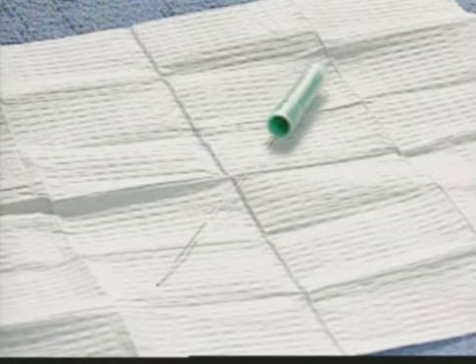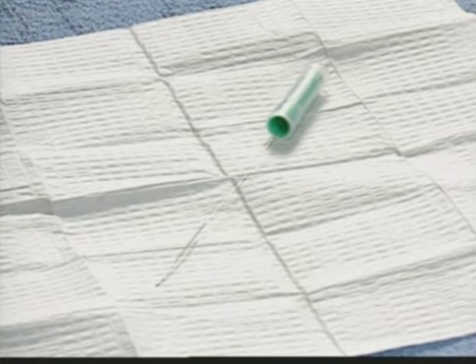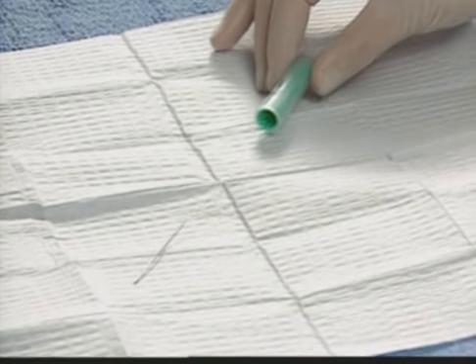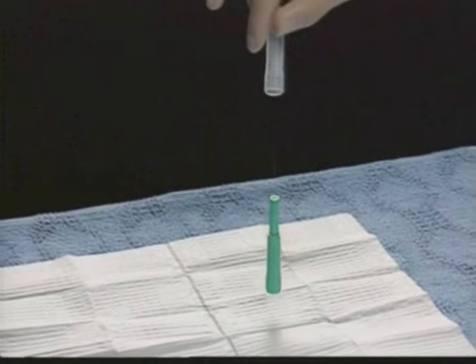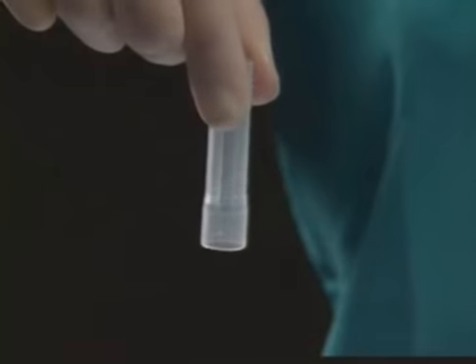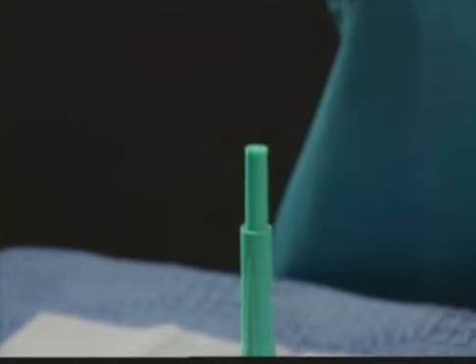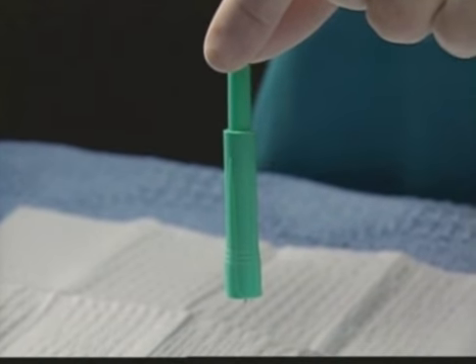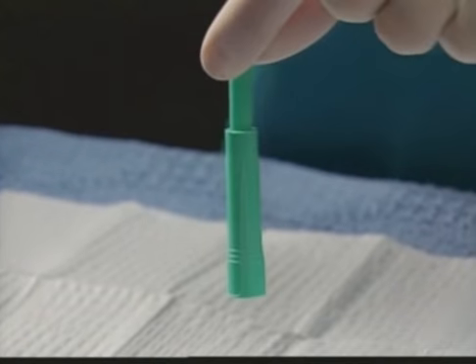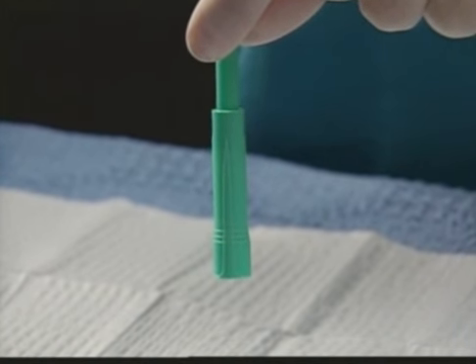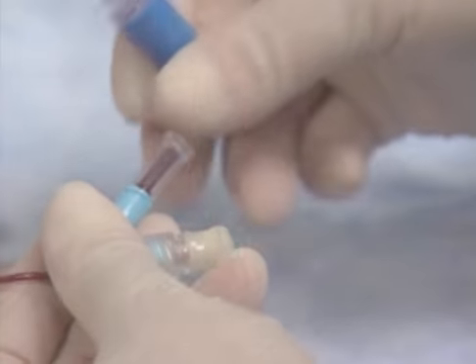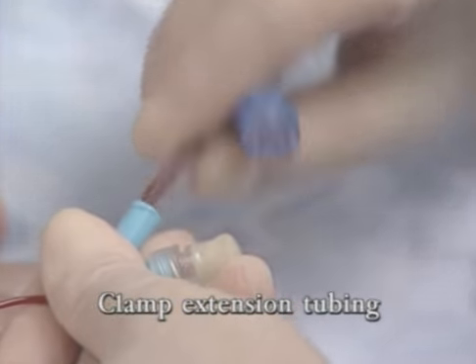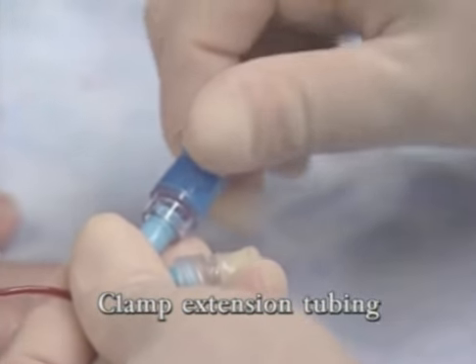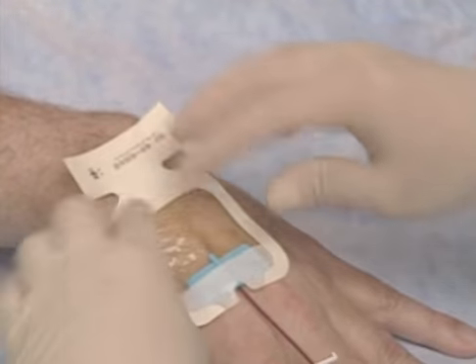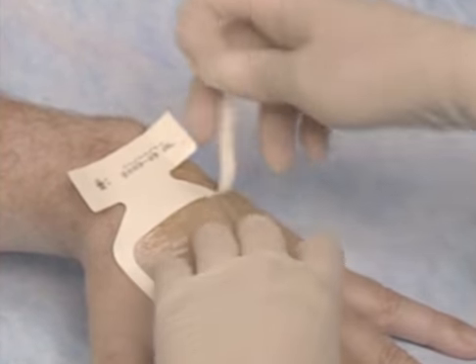If for some reason the needle is not shielded after removal, grasp the pebbled end of the white safety shield, allowing the needle to hang downward. The telescoping shield should fall and cover the needle. If the tip is not completely covered, grasp the upper end of the telescoping safety shield and gently push downward, keeping the needle point away from your body at all times. Dispose of the entire unit immediately. Remove the vent plug and connect the IV catheter to a primed IV set or needleless injection cap and secure the catheter according to your facility's policy and procedure.